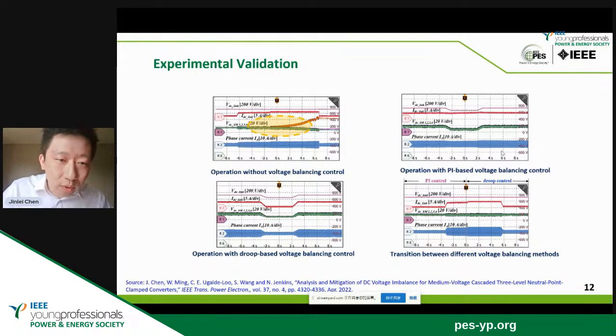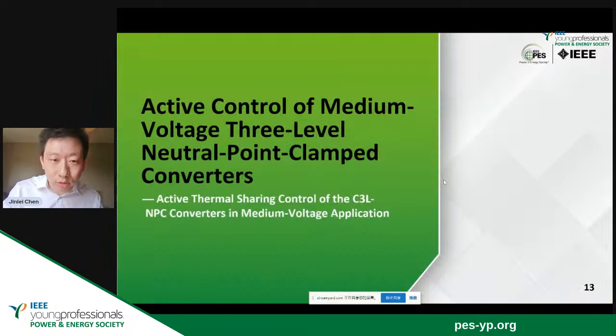This is an experimental validation. First, without using the voltage balance control, we can see that the DC voltages of the submodules diverge as time goes on, which implies the system instability. After using the PI-based voltage balancing control and the droop-based balance control, the DC voltages of submodules can be balanced effectively, and the system is stable. The last part shows the transition between different control modes. We can see that the transition is smooth, and there are no oscillations in the transition between the different control modes.